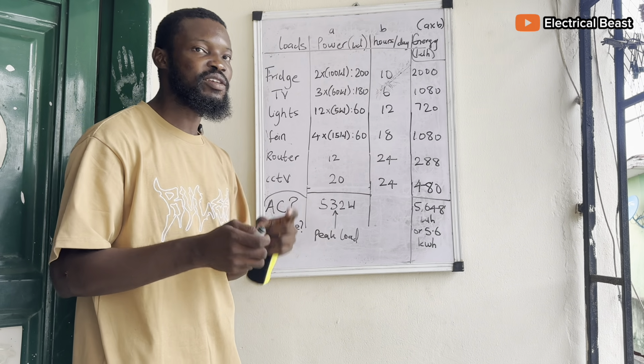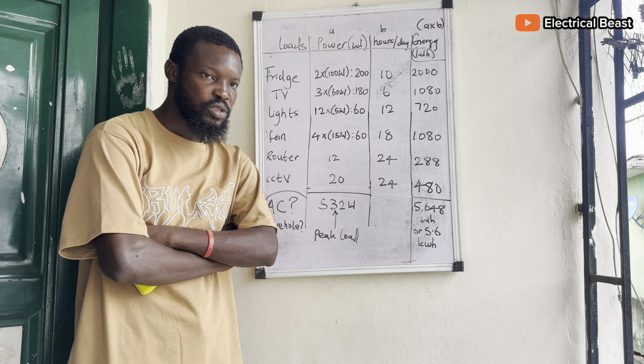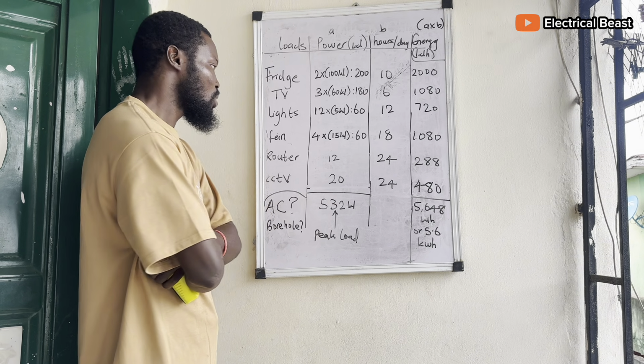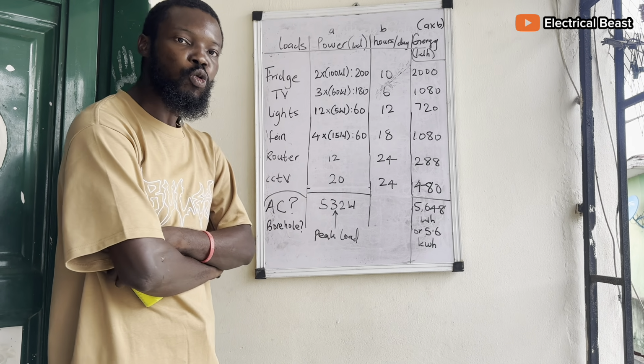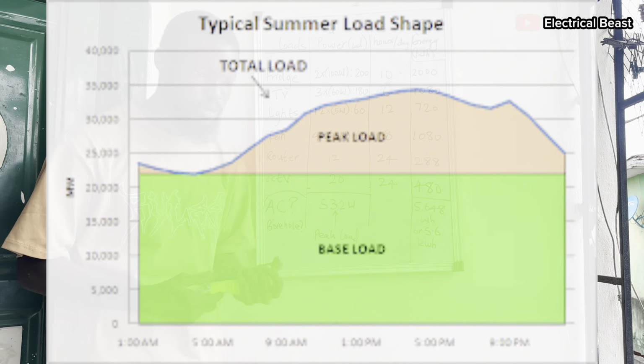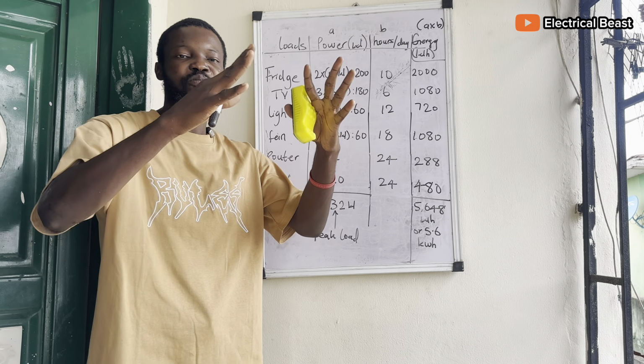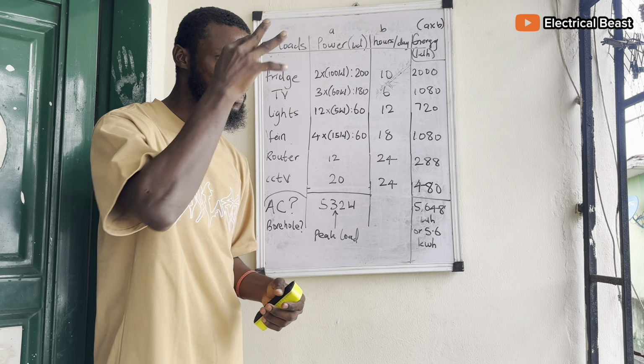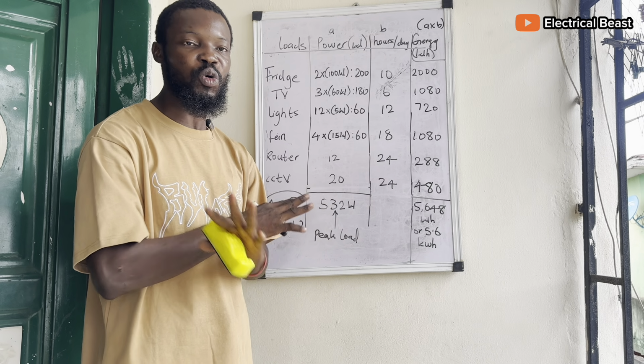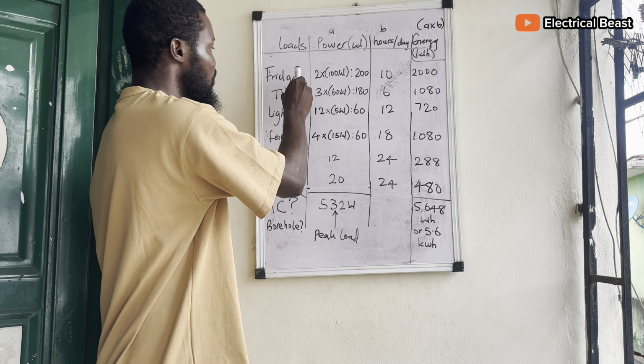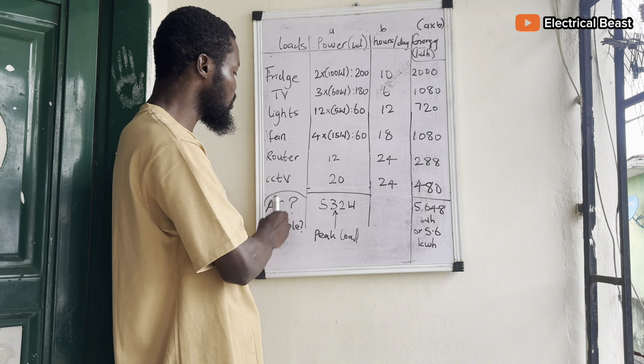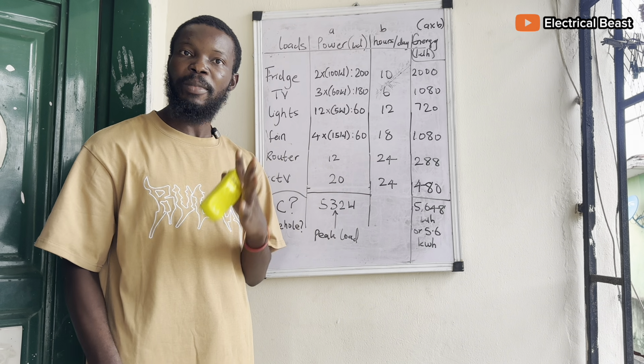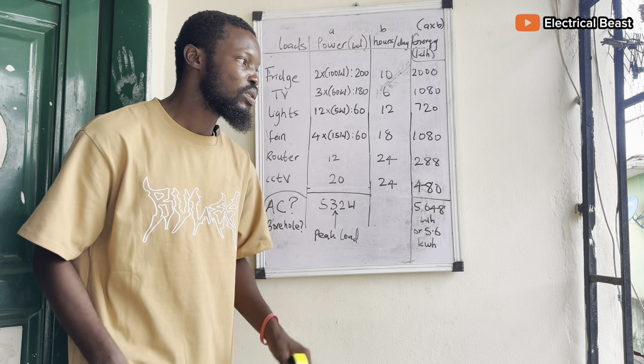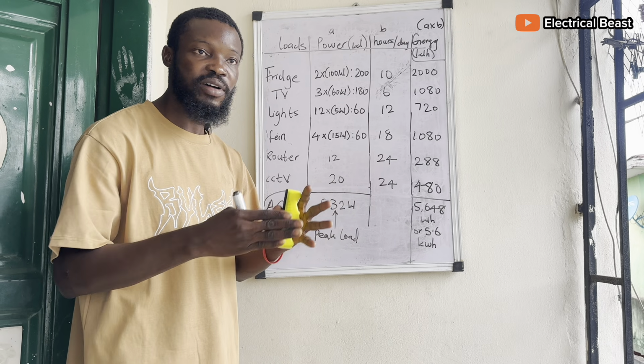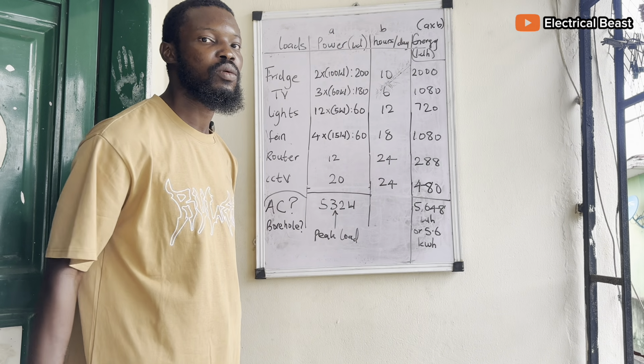Now, let's go to your inverter sizing. That's the first thing we need to do: how to size your inverter. What you need to know is the peak load. What is your peak load? Your peak load is the total amount of power that all your loads will consume at the same time when they are switched on. If you switch on all your refrigerators, all your TVs, your lights, your fan, your router, and CCTV, you want a situation whereby if all your loads are on, there's enough space for your inverter to be able to power everything without stress, without overload. So that's your peak load.